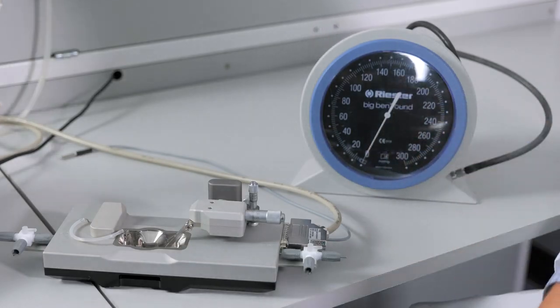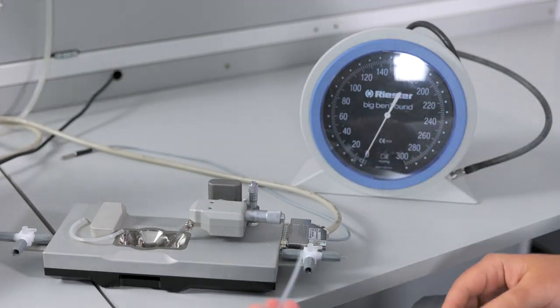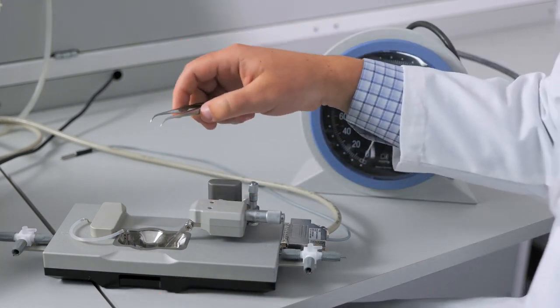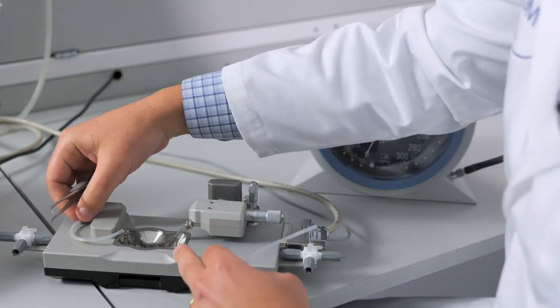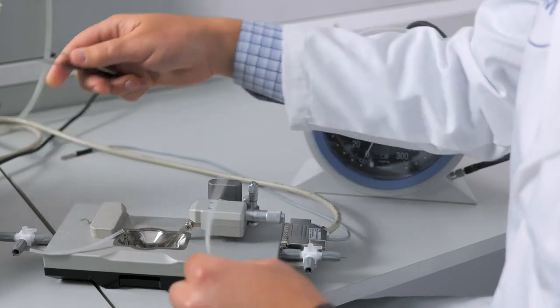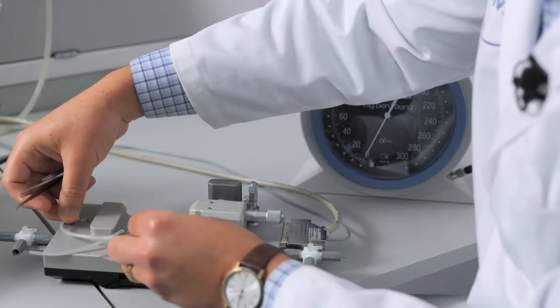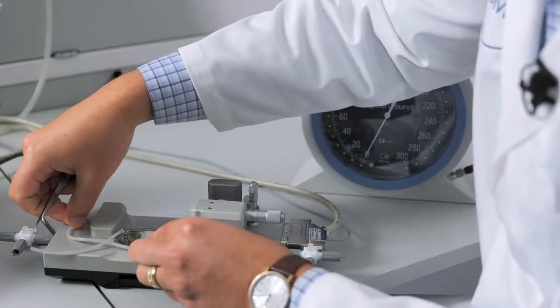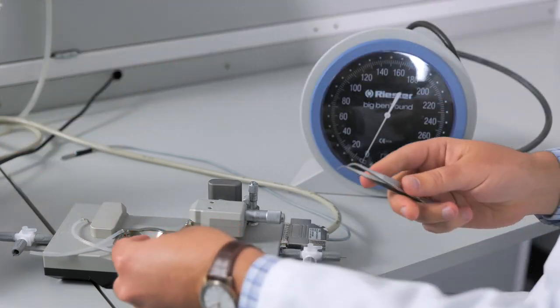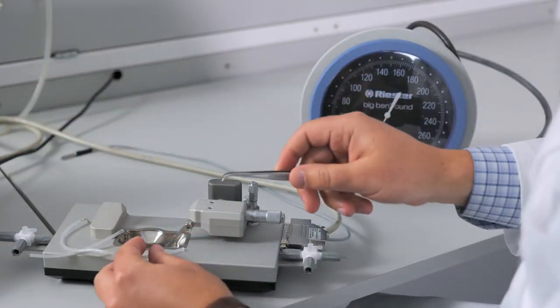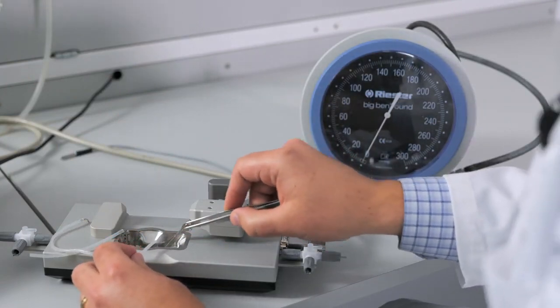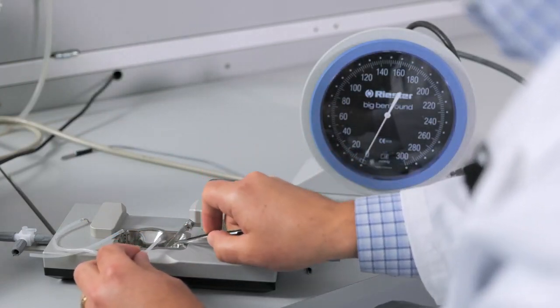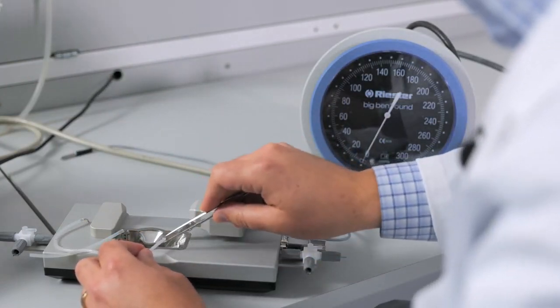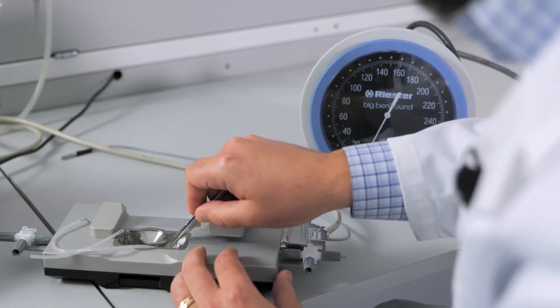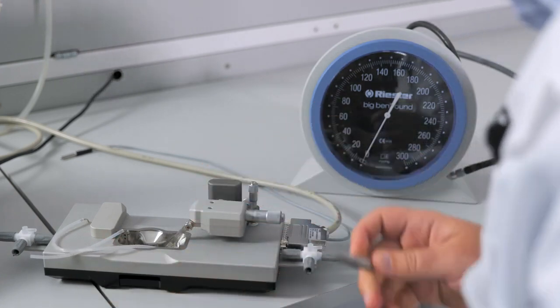To set up the chamber for the calibration, you need to place your calibration shunt on the chamber, bypassing the cannulas. So we will disconnect the left side cannula mount tubing and attach the calibration shunt, and then using your non-dissection forceps, place the calibration shunt on the right side, bypassing that cannula.